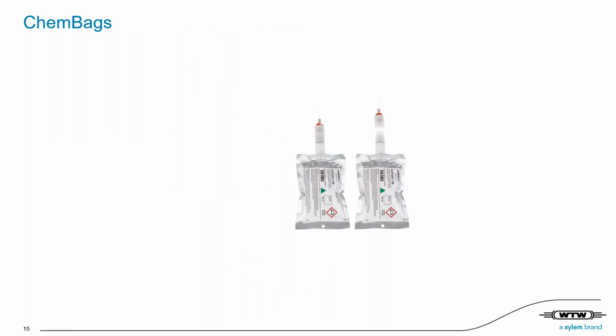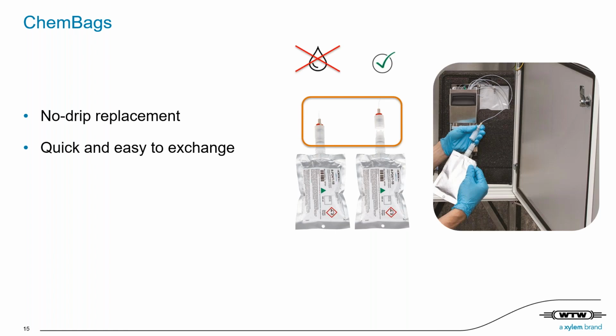Another unique feature of Alyza IQ are the ChemBags. Instead of conventional reagent containers or bottles, these bags are used to hold the chemical solutions. With a total volume lower than 200 milliliters, they can be easily stored and transported globally. With the unique connector as shown here, which is specifically designed for the new analyzer, the reagents can be exchanged easily and drip-free. The connector is automatically open and closed so that you never get in contact with chemicals. And you don't have to worry about spilling solution bottles or something like that.